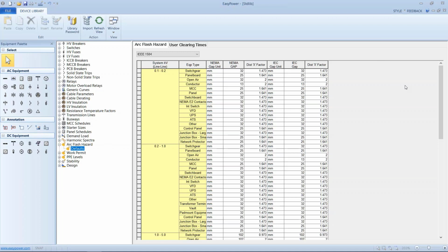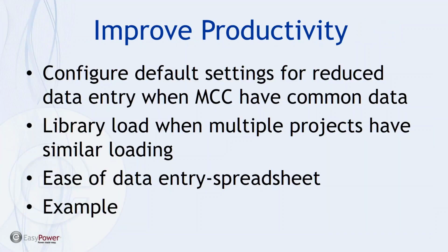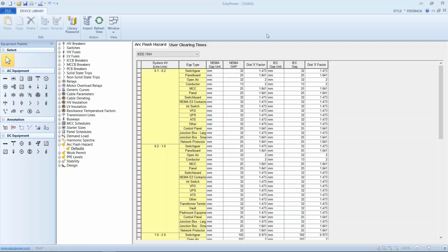Now, if I jump back to my presentation, one of the ways you can deal with this, because we're talking about having to set each bus with these elements, is that you can actually set the default settings for your motor control centers. If you have several of the same type, or if you frequently use the same configuration, you can use motor control center designation as your default settings. So let me run through this briefly.